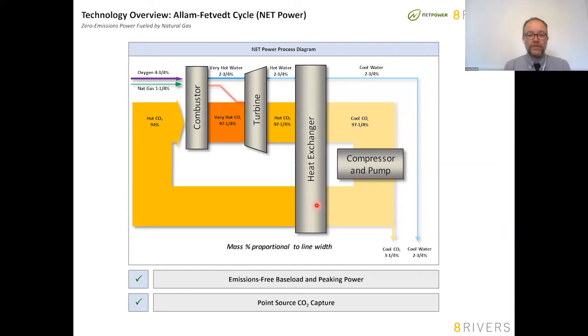Also, for people who have been around CO2 power cycles, you're aware there's a thermodynamic difference - the specific heat of low pressure CO2 is different than the specific heat of high pressure CO2. There's an energy imbalance between the two, and this imbalance shows up in the heat exchangers. In order to correct the heat exchangers and make the cycle more efficient, closed loop CO2 cycles will generally have a recompressor or a hot gas compressor to fix the thermodynamic balance of the heat exchangers.